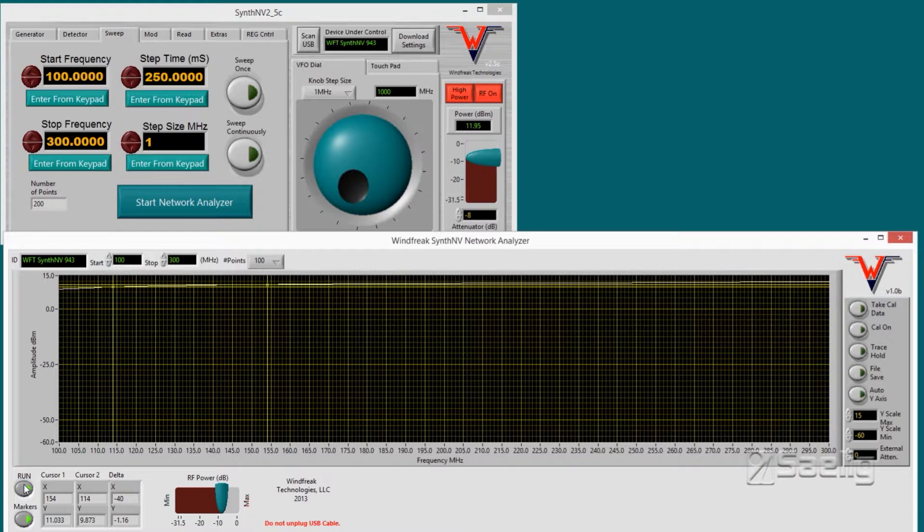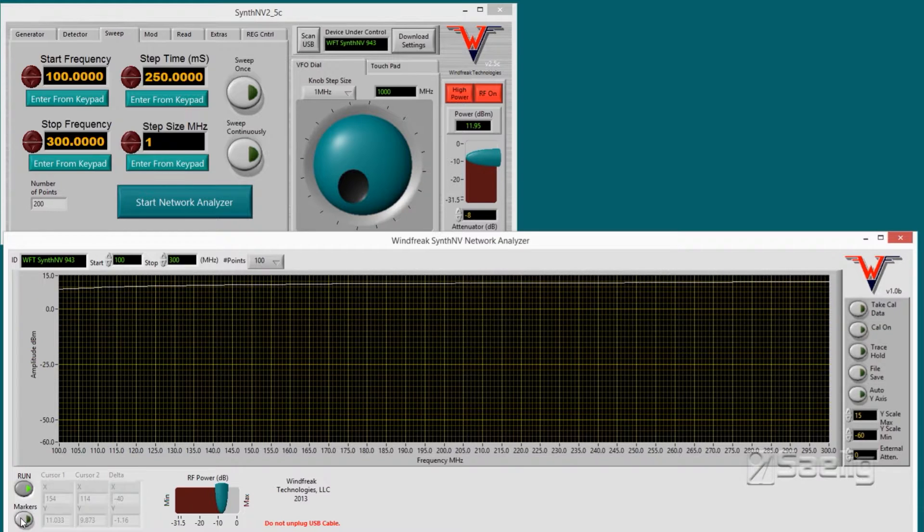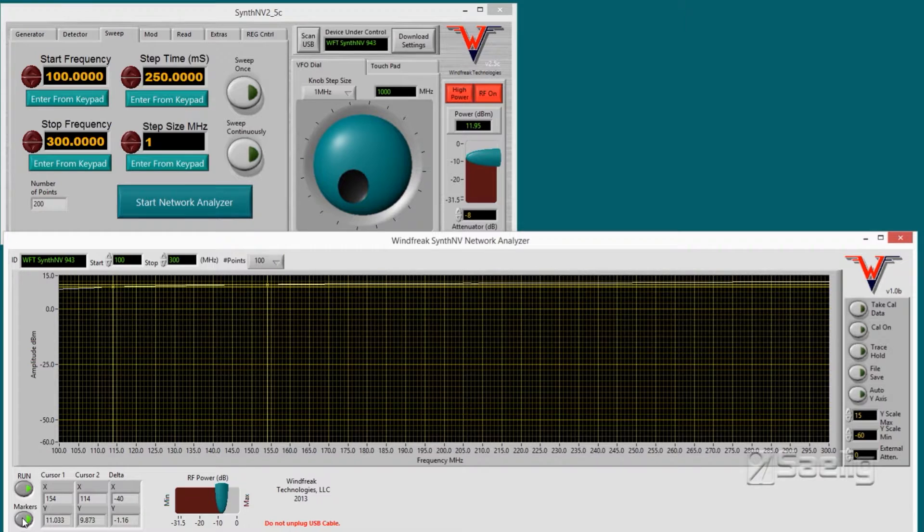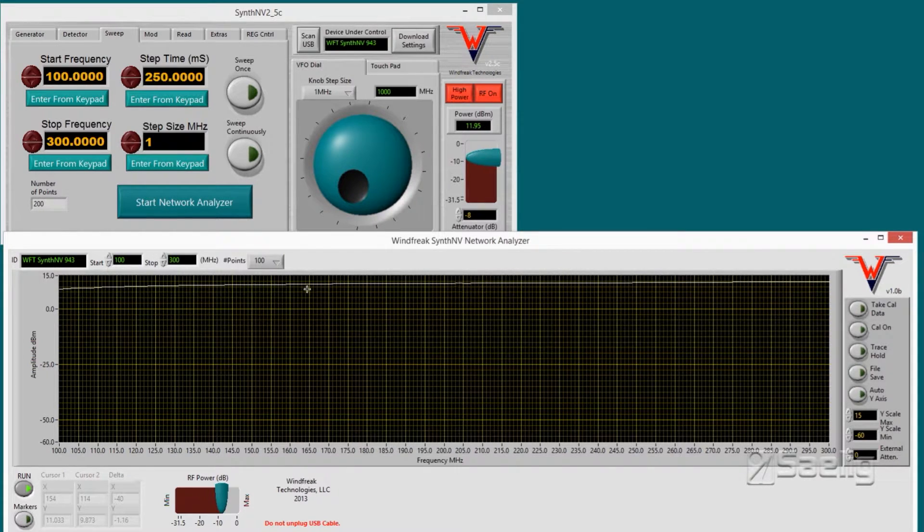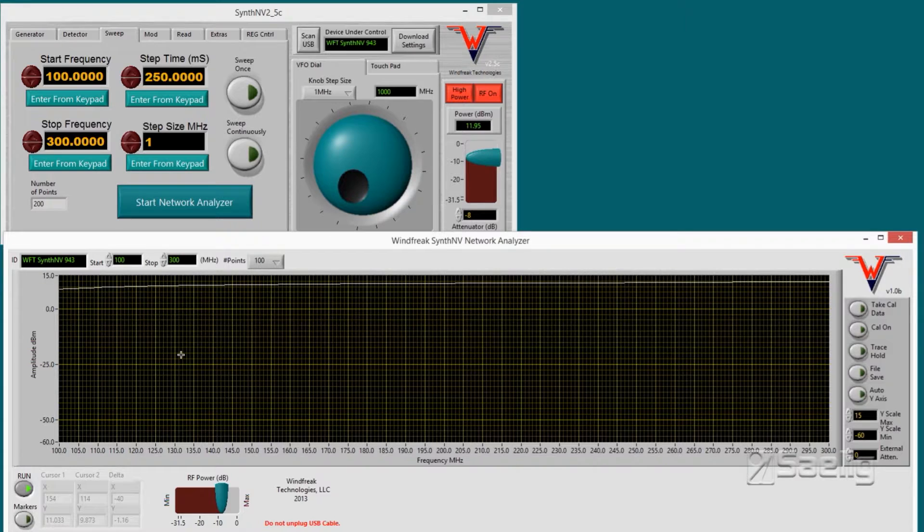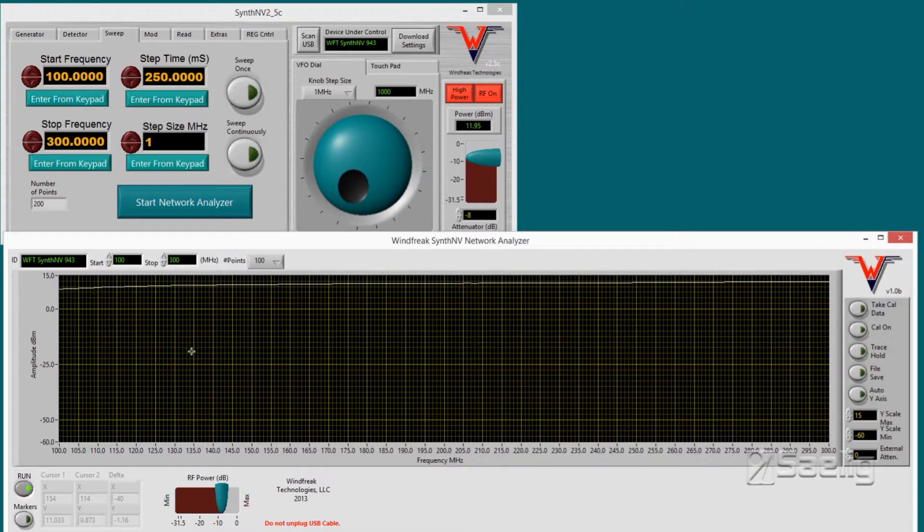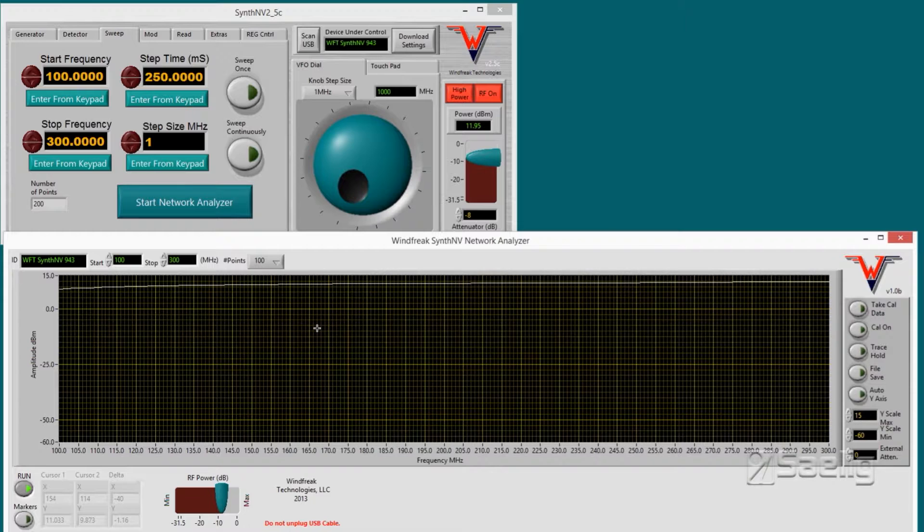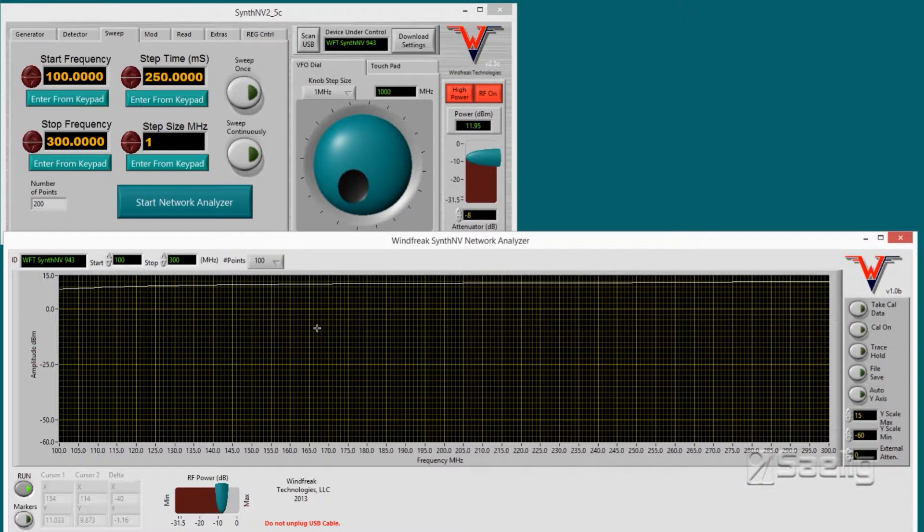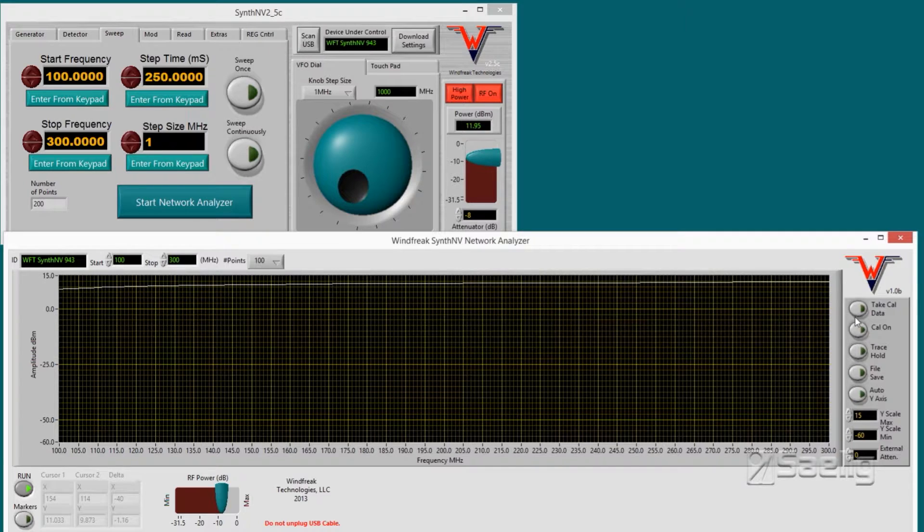And then down here in the lower left hand corner there's the run stop control, and there's also controls for turning your markers on and off. I'm going to turn the markers off because I want to draw your attention to the white line at the top there. This is the uncalibrated response. So in order to cal the system you attach a good quality cable from the RF generator output to the RF power detector input directly.